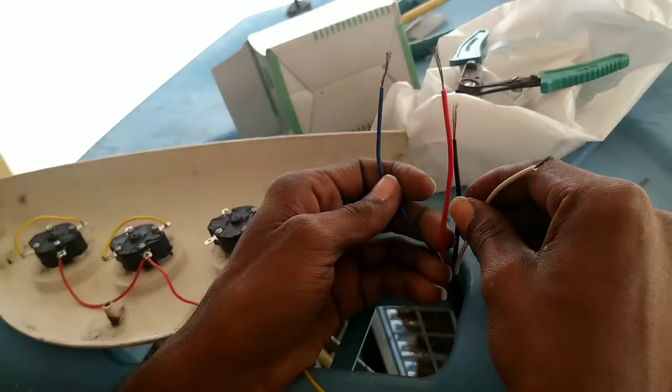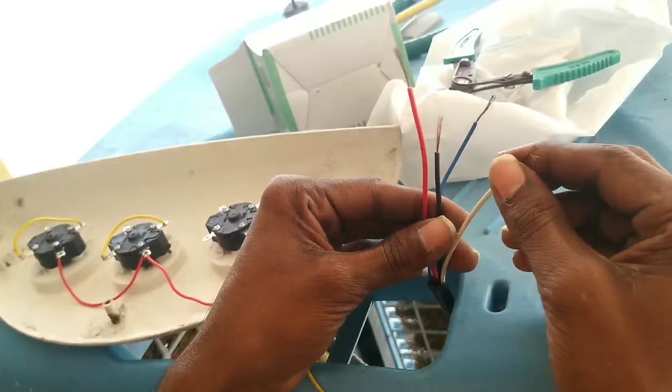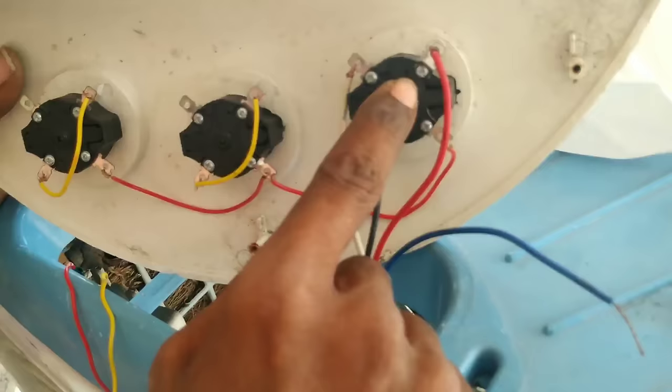The four wires are out. Blue is the common wire, friends. We have to connect the motor speed through the side. The red one is speed 1, white one is speed 2, and black one is high speed. Connect the motor wire here: 1-1 red, 2-1 white, and 3-1 black. The remaining blue is the common.